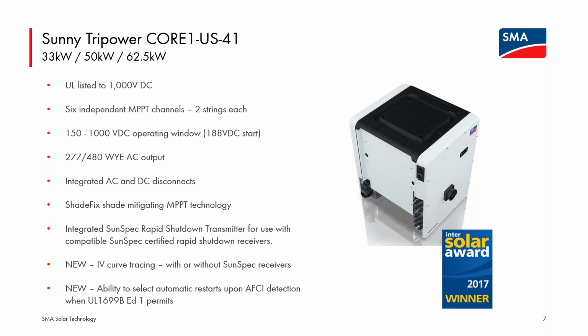The products look identical. So for all the power classes, the spec sheets, the number of inputs, all of that remains identical across the line. That is just the AC power limit that is different between the different units. The architecture of the inverter, as this was primarily aimed for commercial rooftop, was around design flexibility to allow designers to place PV modules across a commercial rooftop and attempt to fill all addressable space with PV modules while working around any obstacles on the roof, such as stairwell access, skylights, HVAC units, and maybe code mandated walkways, where you have to break up the array every so often.